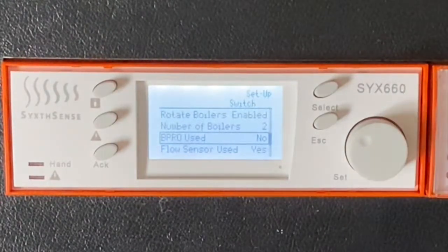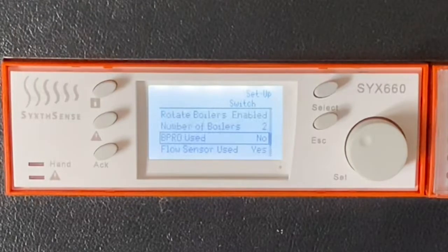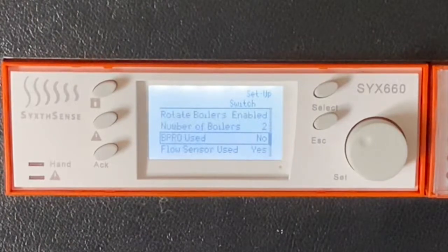Boiler Pro used is a feature of the controller where we have a 0 to 10 volt output, and we can send a 0 to 10 volt demand signal to a boiler step controller from the Boiler Pro range that we offer, as in SYX660. We have a number of Boiler Pro modules which can cater for different types of boiler and different types of loads that boilers can present to us. So 0 to 10 volt sequencers or high-low fire boilers, etc.